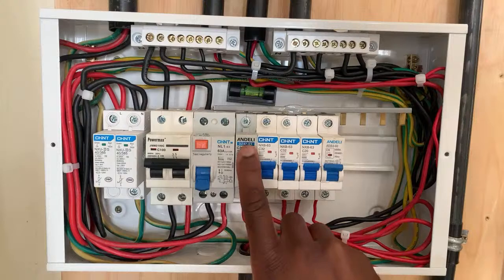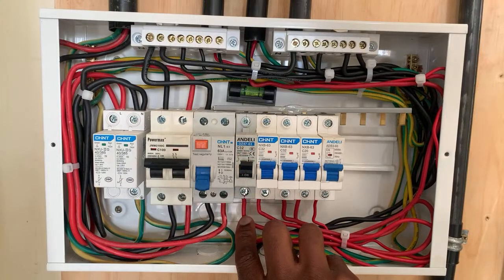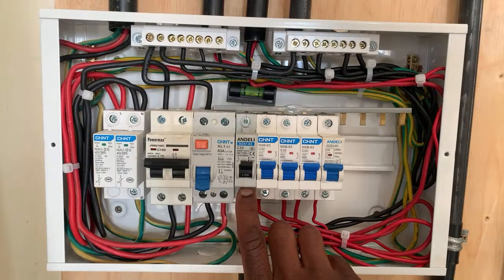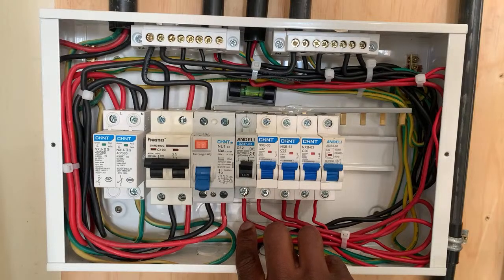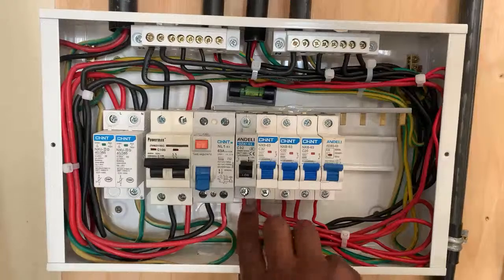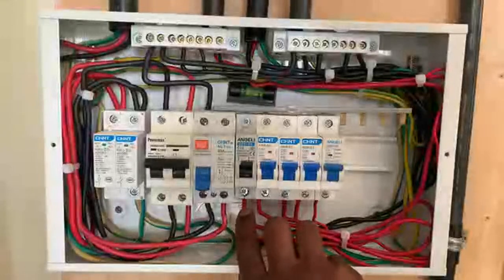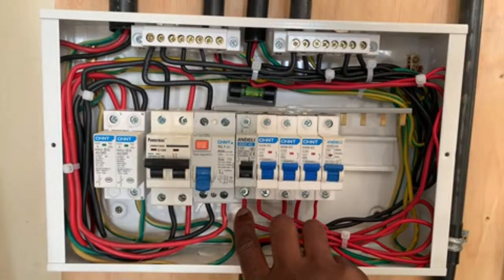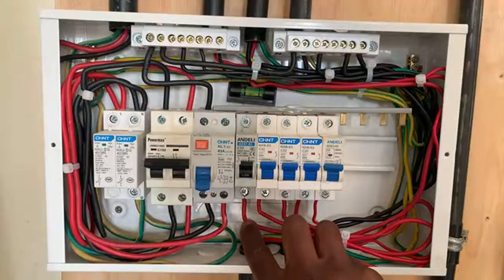So you might have the correct cable size, you might have the correct MCB in terms of the sizing, for instance a 32 MCB. You might have a quality material that has made that cable, but my good friend, if you make a mistake of screwing on the insulation, or you make a loose connection here, then your quality MCB and your quality cable are useless, because that strain in electricity flow will lead to overheating, because the surface area is not well covered here. That will essentially mean that the size is compromised. The correct size of a cable will definitely affect how electricity is conducted. That will mean heavy resistance will be witnessed there.